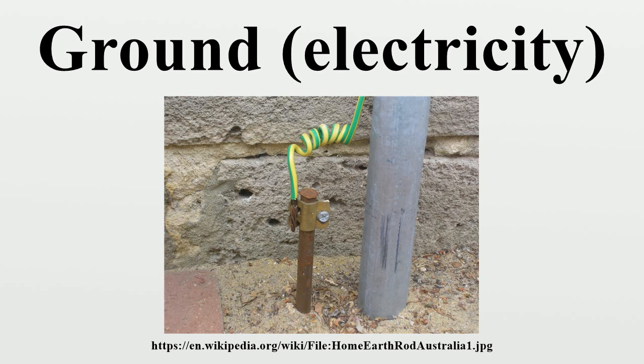Earthing systems in electricity supply systems. An earthing system defines the electrical potential of the conductors relative to that of the Earth's conductive surface. The choice of earthing system has implications for the safety and electromagnetic compatibility of the power supply. Regulations for earthing systems vary considerably between different countries.